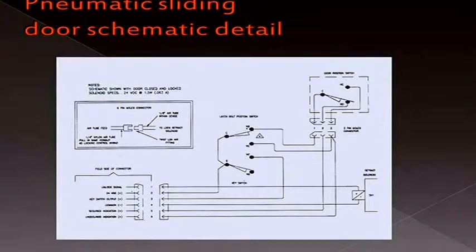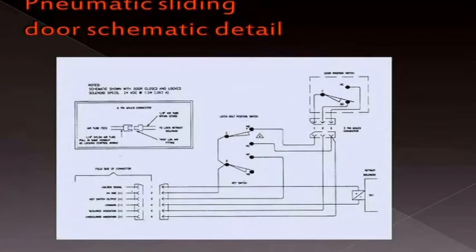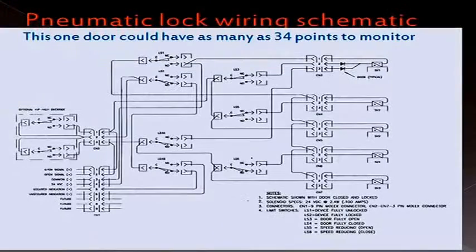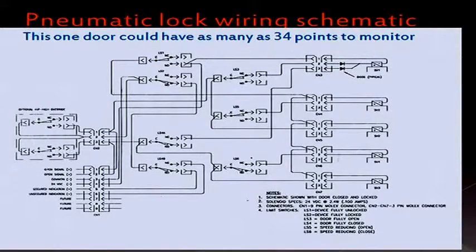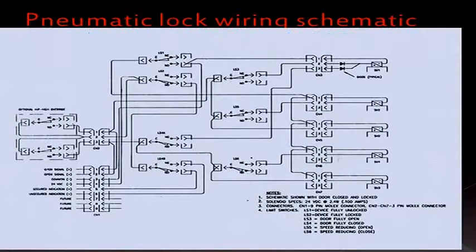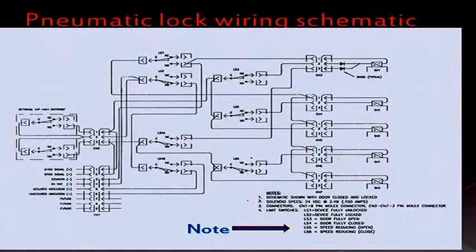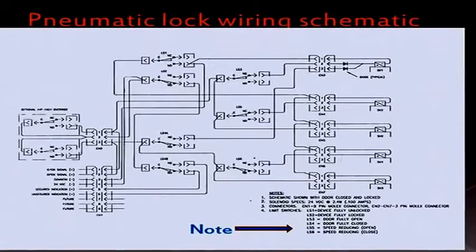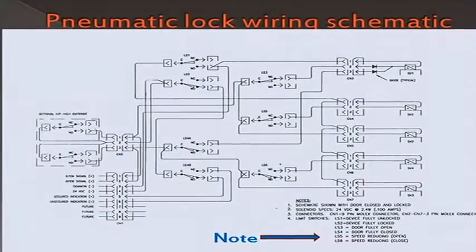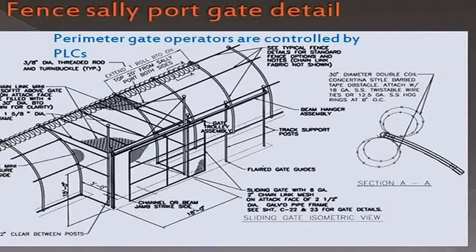A lot of times PLCs are implemented to cut down on hardware costs — conduit and actual wiring. You can run all these wires back to central control from every single point, or you can run them to a PLC and run one wire back to central control. The motors on the doors can be controlled to adjust speed — you could crank it up and essentially blow out the motors on the doors, making them no longer functional. It's called a cascade program so the doors don't all open or slam at once. The perimeter fences also have intrusion detection systems.